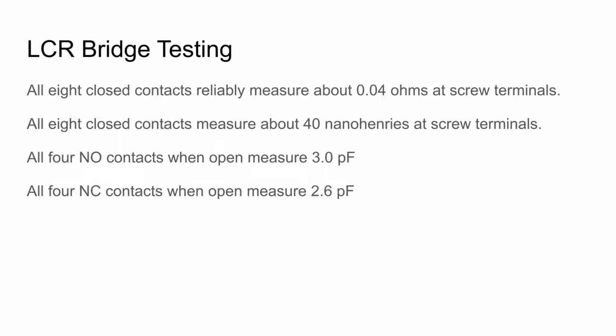I found that very reliably the normally open contacts when open measure 3 pF almost exactly, and the normally closed contacts when open measure 2.6 pF. I'd attribute the difference in capacitance to some kind of internal hardware design, relay construction, something like that. It's very consistent. To give that some kind of useful application, consider the capacitive reactance of a 3 pF cap is about 1750 ohms at 30 megahertz, or almost exactly 50 ohms at 1 gigahertz.